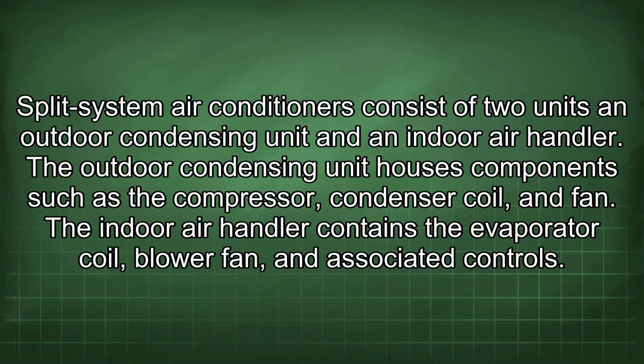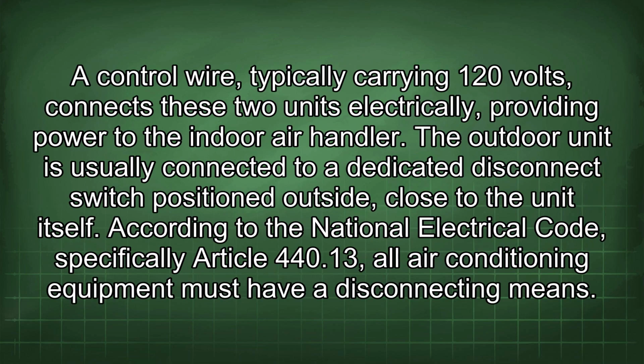Split system air conditioners consist of two units, an outdoor condensing unit and an indoor air handler. The outdoor condensing unit houses components such as the compressor, condenser coil, and fan. The indoor air handler contains the evaporator coil, blower fan, and associated controls. A control wire, typically carrying 120 volts, connects these two units electrically, providing power to the indoor air handler.